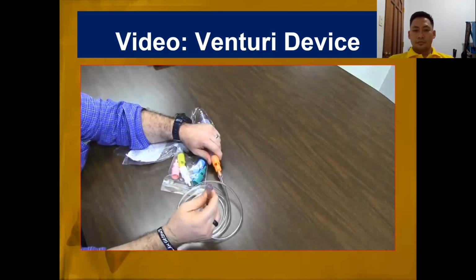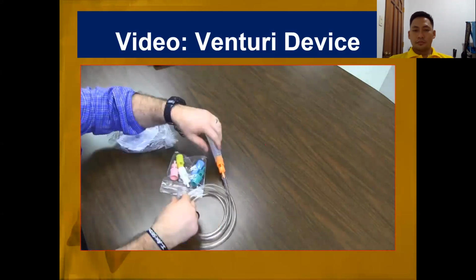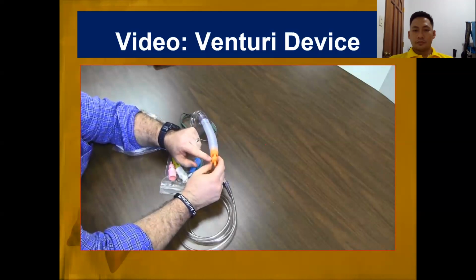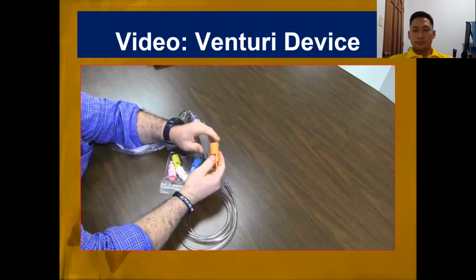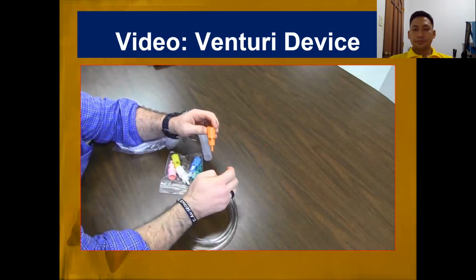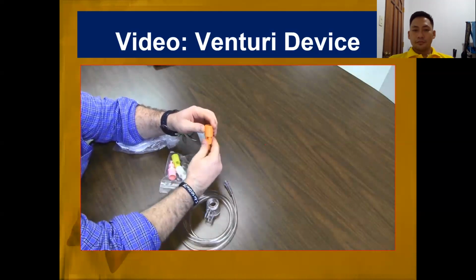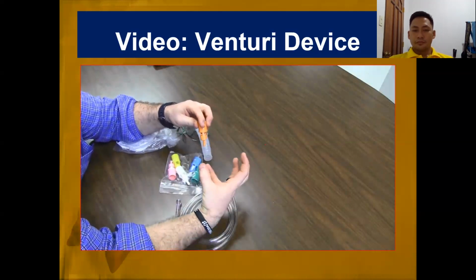From our flow meter comes 100% oxygen down the tube through this fixed orifice, at a specific flow, at 15 liters. And the really cool thing about this device is that when that comes at 15 liters at 100% through the center hole, since this is 50% oxygen, it's going to pull in the exact amount of air to...